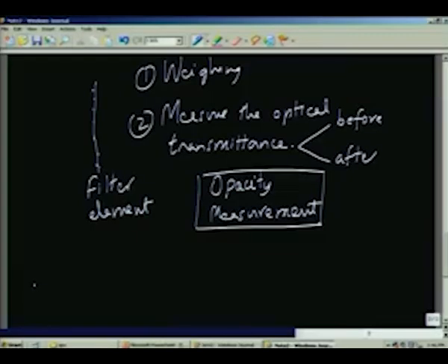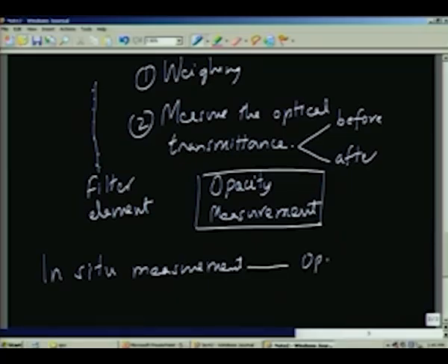The other method is in situ measurement, which again uses opacity measurement, but not opacity of a filter element, it uses the opacity of the gas itself, the opacity of the particle laden gas.